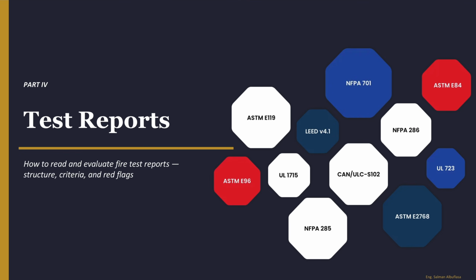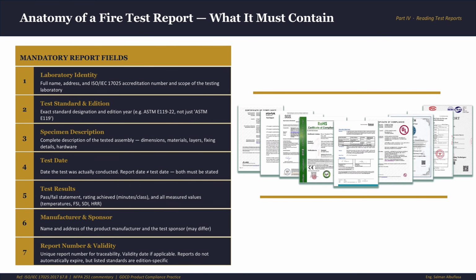Alright, we are now almost past the second half of our presentation. The anatomy of fire testing reports. A fire test report is not a marketing document. It's not a data sheet. It's not a catalog. It's a legal instrument. Proof that that specific product in a specific configuration was tested under accredited conditions and generated results. And it must contain 7 mandatory fields.